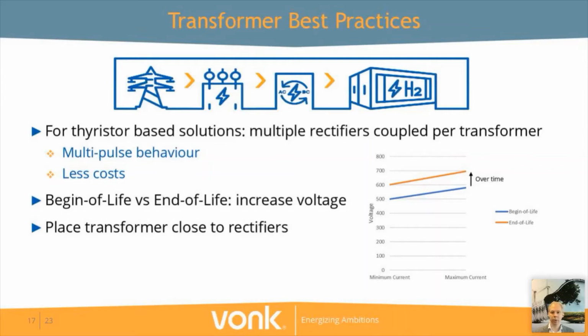In many cases, where you have a single power supply in place, you often have one transformer and one rectifier. However, due to the nature of the power supply of the electrolyzers, where you have often multiple trains in series, what you can do is apply multiple rectifiers, for instance 2, to one transformer. This has the advantage that you can simulate multipulse behavior, so a power quality improvement, as well as that you have less cost. And this is basically driven because you have one transformer less. Less equipment means less cost.